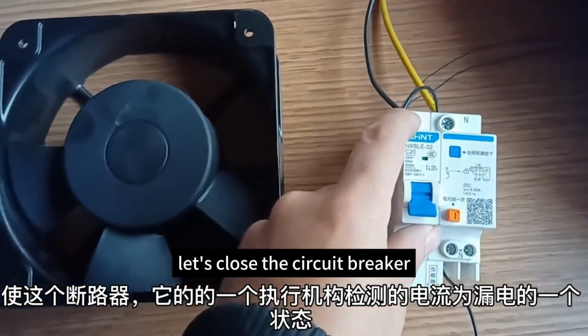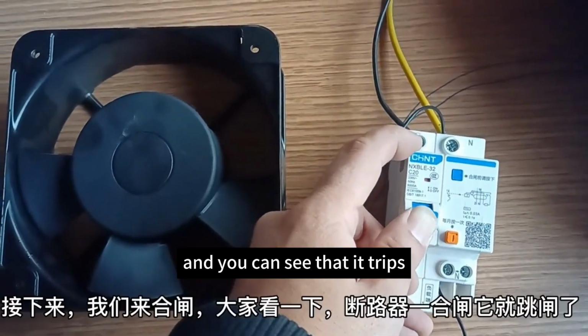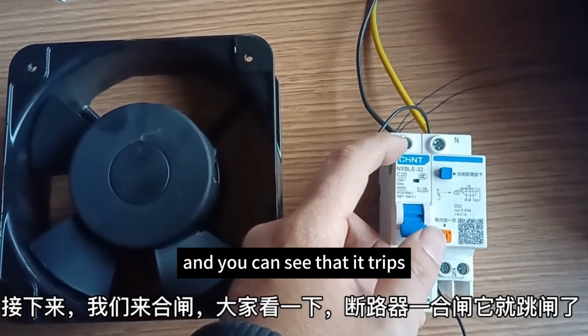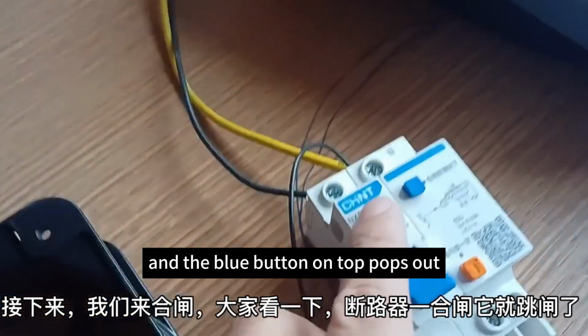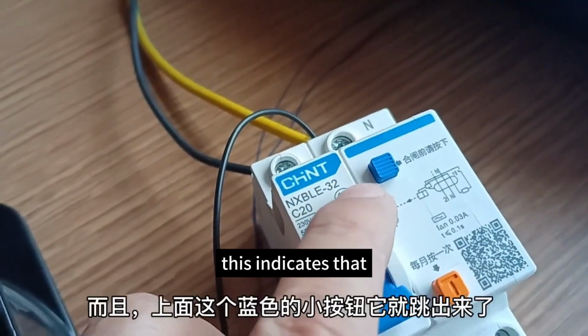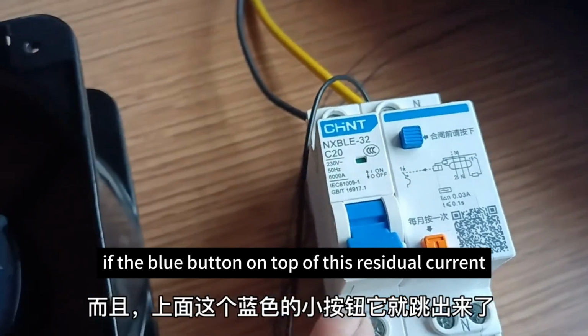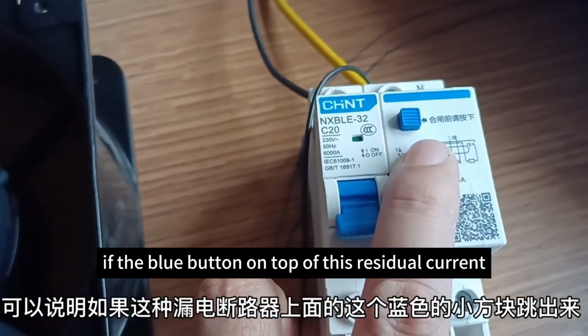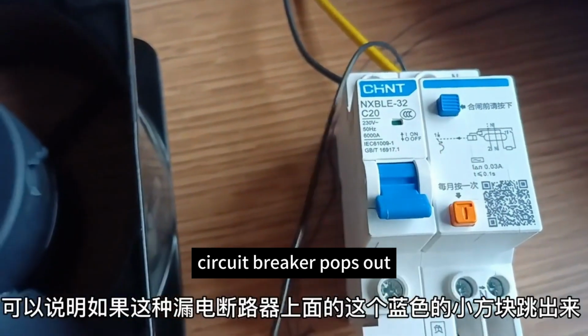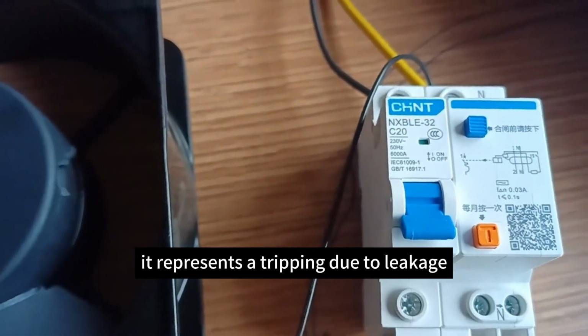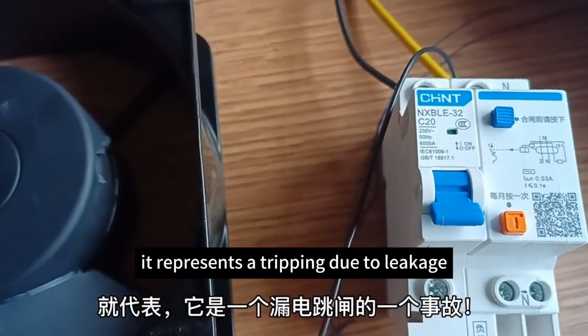Let's close the circuit breaker, and you can see that it trips, and the blue button on top pops out. This indicates that if the blue button on top of this residual current circuit breaker pops out, it represents a tripping due to leakage.